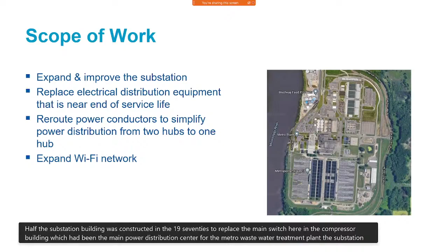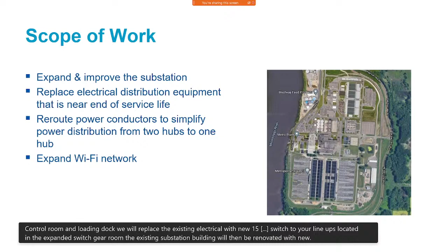This project expands the main substation building to the north, including a new cable vault room, switchgear room, control room, and loading dock. We will replace the existing electrical gear with new 15 kilovolt switchgear lineups located in the expanded switchgear room. The existing substation building will then be renovated with new HVAC equipment, a new storage room, and space for a generator bus.